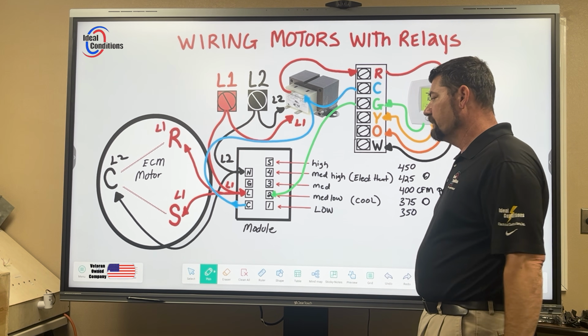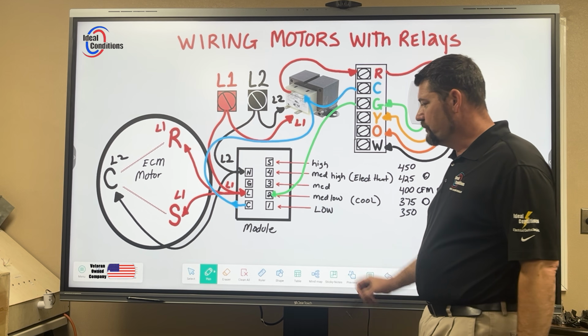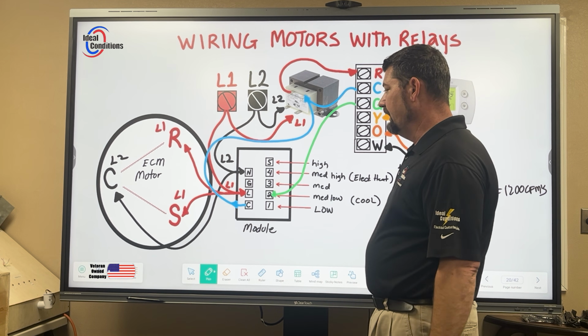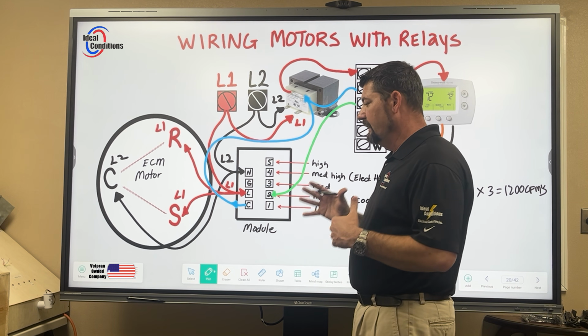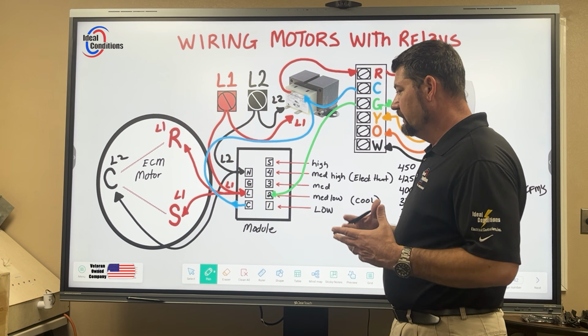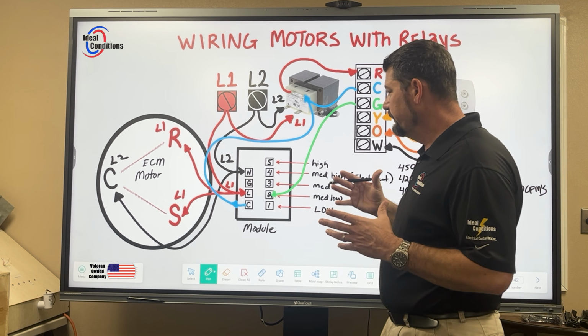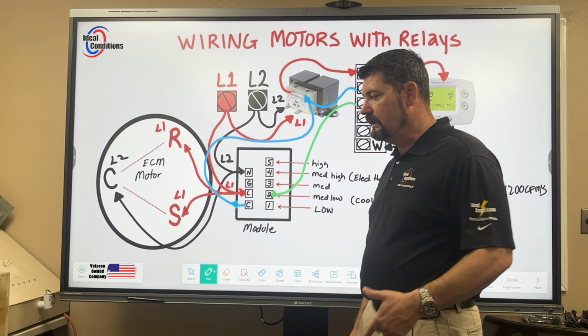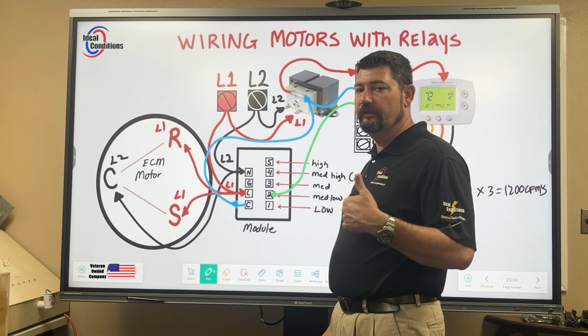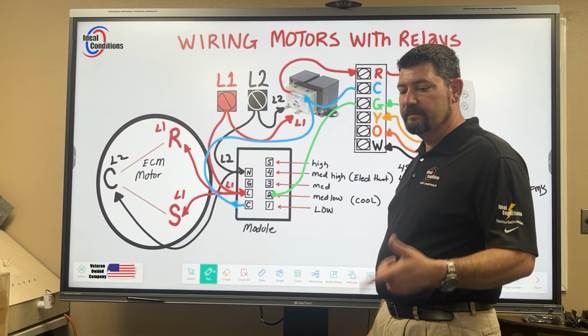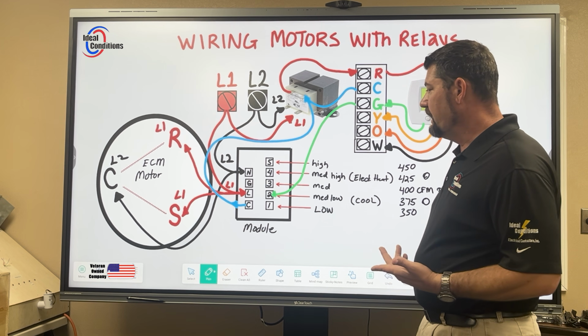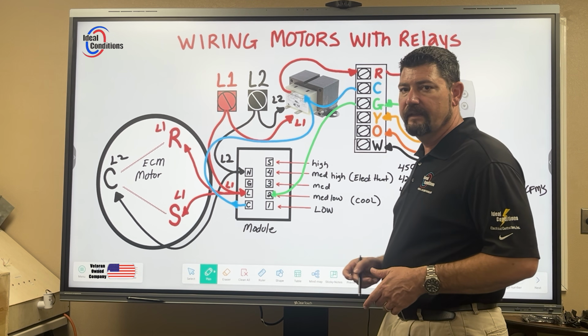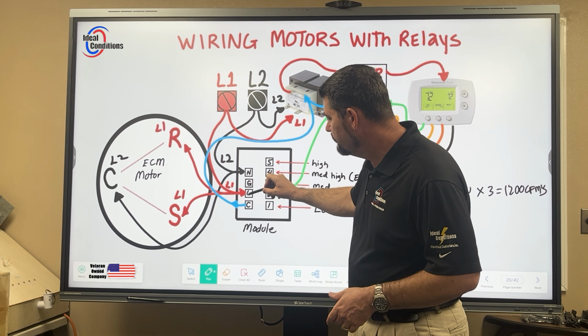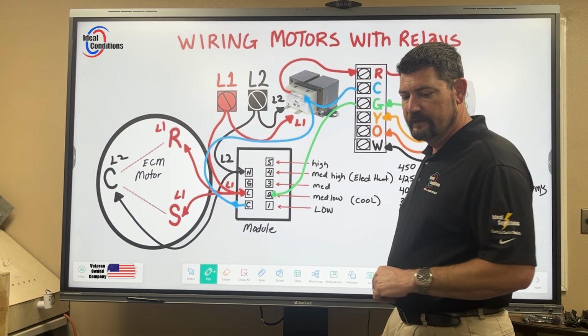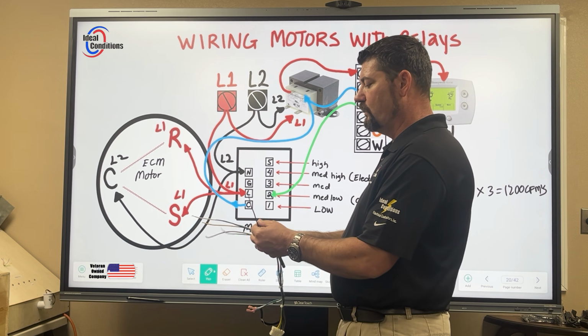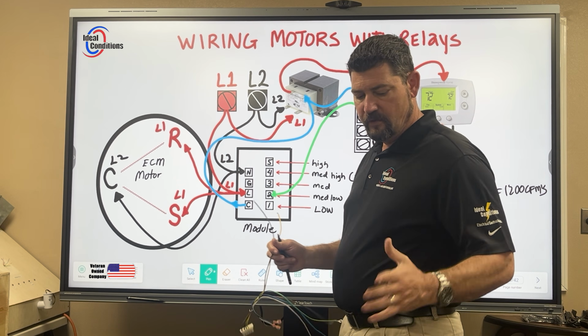If you feel you have a bad motor and you're putting voltage on these and the motor's not turning, and it's a warranty item and the manufacturer needs to know, is it the module, is it the motor? Simply detach the module from the motor and go ahead and do that brake test that we talked about and see if you have an open winding on the motor. If your winding is open, okay, then it's going to free spin. Now, if you try to jump L and N out together, which on the plug will be the black wire and the yellow wire, you tie these things together, you are not going to get a brake test out of that.